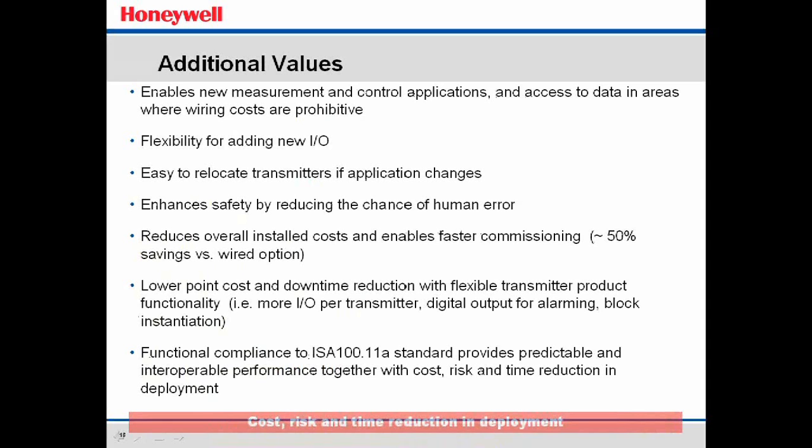And then the expanded use of the 1-second update rate. We worked very hard to make the 1-second update rate system-wide while still maintaining an acceptable battery life. So while it's not the 4 to 5 years that we expect out of a normal battery, it's maybe 2 to 3 years in good conditions. But that's still a pretty acceptable battery life out of a 1-second update rate transmitter.